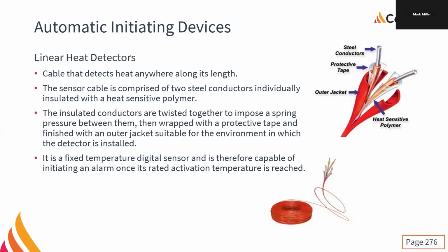And anywhere that you run sprinklers, you run linear heat detection because it's a lot more sensitive than the sprinkler heads. So you can catch the fire earlier. This is not so much for life safety in these applications. This is for building safety, protecting the building and its contents versus the people. A cold storage warehouse might be 100,000 square feet and they might have 6 employees. But the stuff inside is worth quite a lot of money.